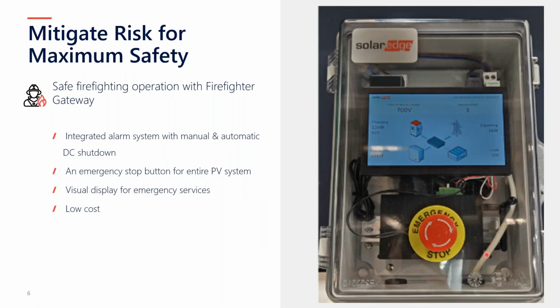It's quite a clever box, because it allows us to do several things. It allows us to communicate with the CSS OD, the battery. It allows us to communicate to meters, now not just one meter, but several meters. And it also allows us to turn off the system and the battery, so the PV and the battery, should there be a fire alarm. So if the fire alarm goes off and the auxiliary contact connected to the One Controller goes off, the voltage will ramp down.